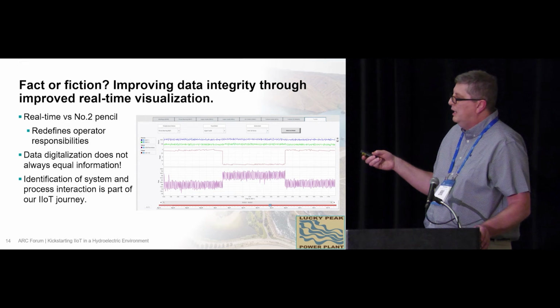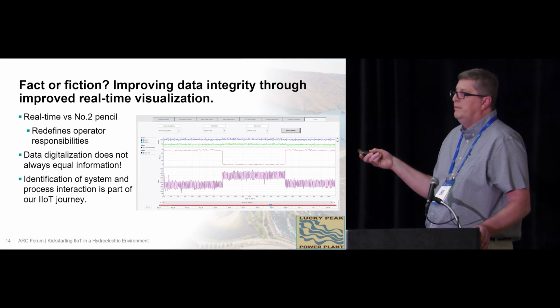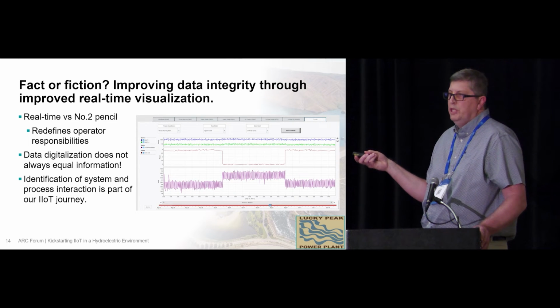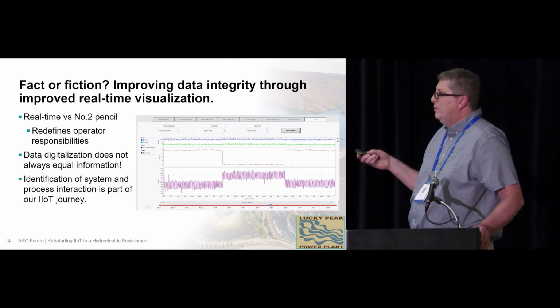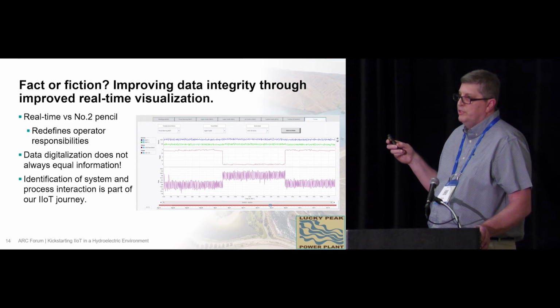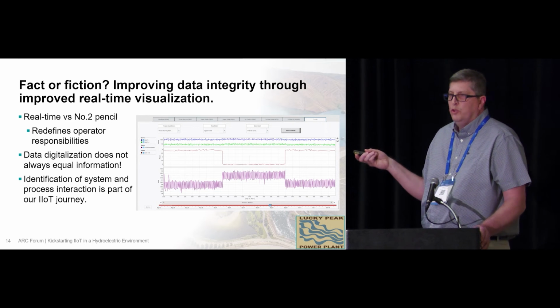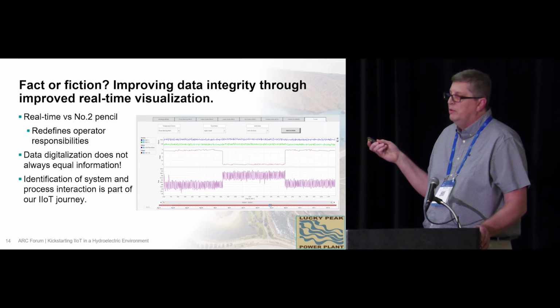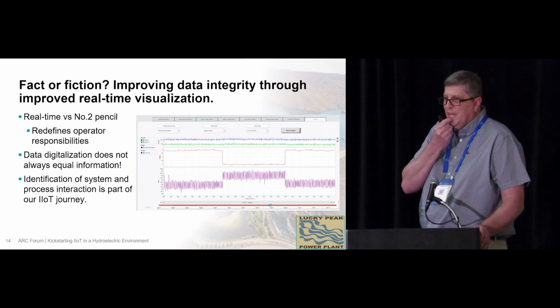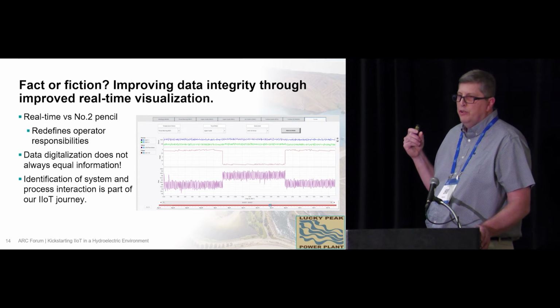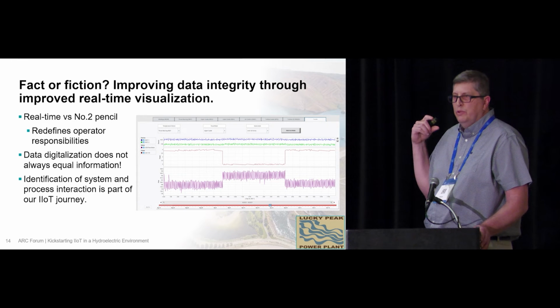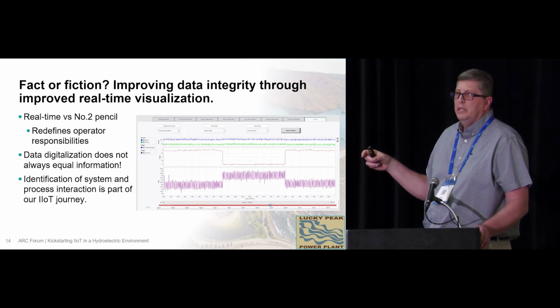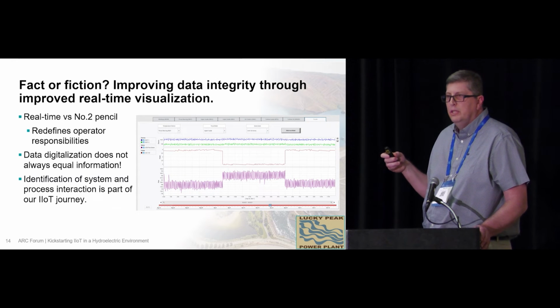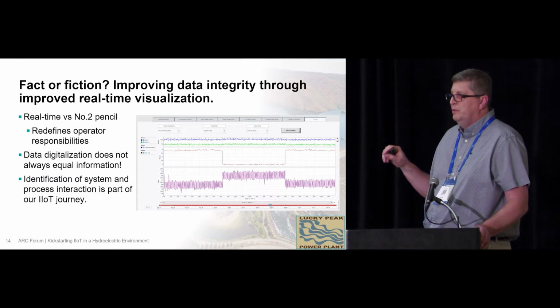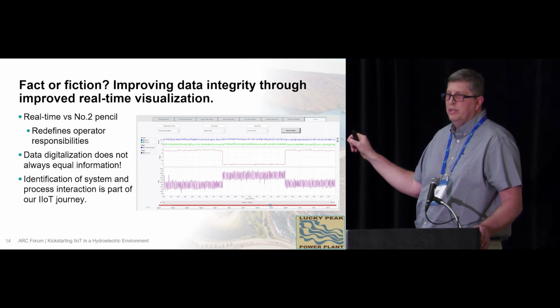I put up this image from a situation during some changes in our generation. At the top we have our temperatures, at the bottom the cooling water for those temperatures, and in the middle our generation. We noticed that when we changed generation, the physics through the penstock and our cooling system changed the cooling water too—something we never would have seen, since we only checked that number once a day at 4 o'clock.